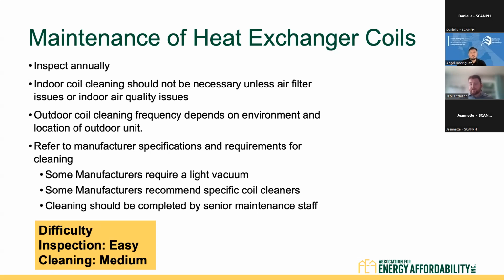You could also consider having a vendor do it. With respect to difficulty, inspection is very easy. Cleaning is medium. You should be inspecting your outdoor coils annually. And for your indoor coils, if you are noticing an issue with air filtration, you should be inspecting it. But if you're properly replacing your air filter every 90 days, or at least inspecting it, you shouldn't have an issue with the indoor coil.